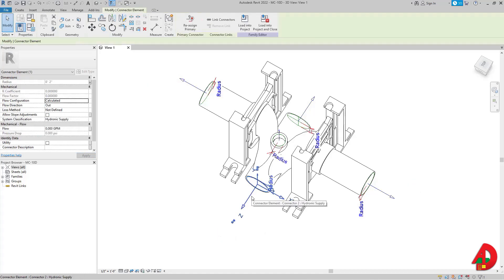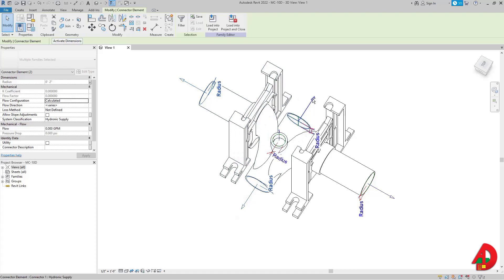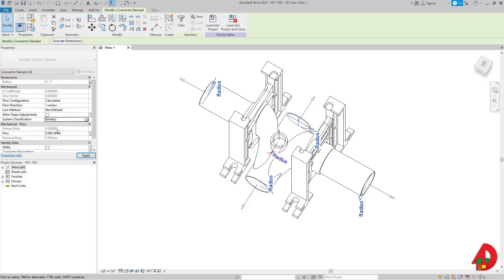Now if I select any of these connectors and look at mechanical flow, I can see flow and pressure drop, but there are no fixture units. That is because the system classification is set to 'Hydronic Supply.' I'm going to select all four connectors — all of them are Hydronic Supply — then drop down and find 'Sanitary.' Now in the mechanical flow I have fixture units, but they are grayed out.